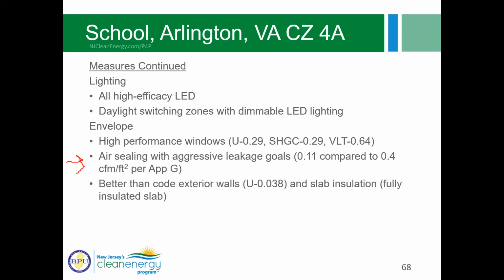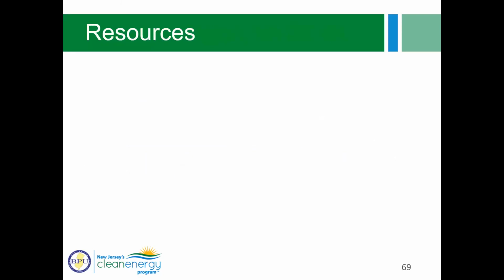And so this sort of ties in with our next discussion of bEQ in that with an Appendix G model, your baseline is going to be gas. And then if you have a heat pump, your proposed is electricity. And some people have a concern about their performance because of that, since electricity is a higher cost on a dollar per kBTU basis than natural gas. And also the source energy factor is higher for electricity compared to natural gas. So sometimes people are concerned about that in terms of performance when using Appendix G, but with bEQ, there's no fuel switching. So that might be a more attractive option. So first I want to touch on some resources and then we'll talk about bEQ.